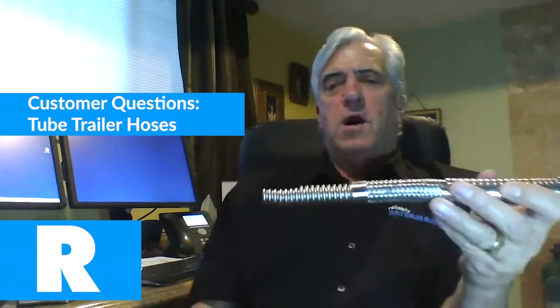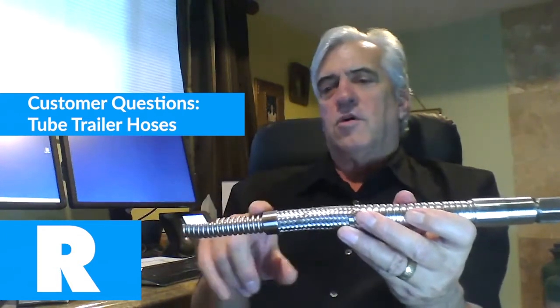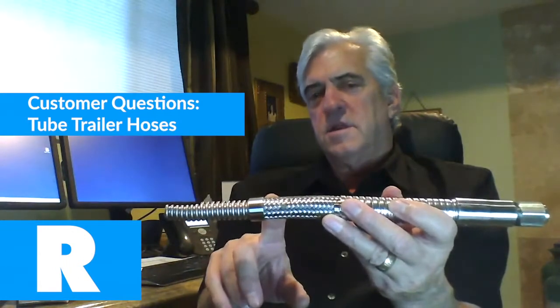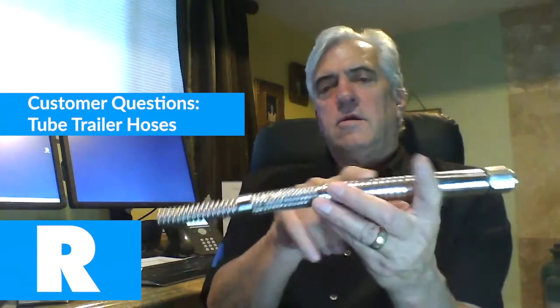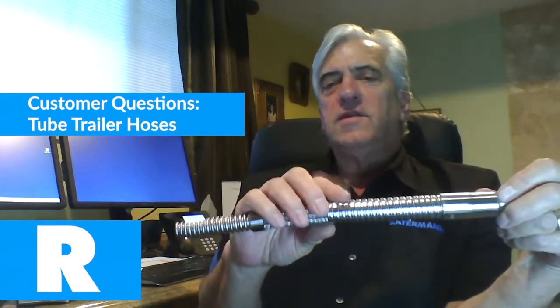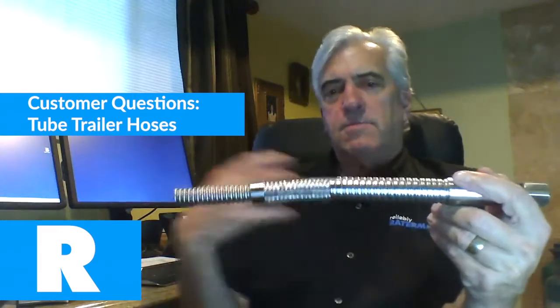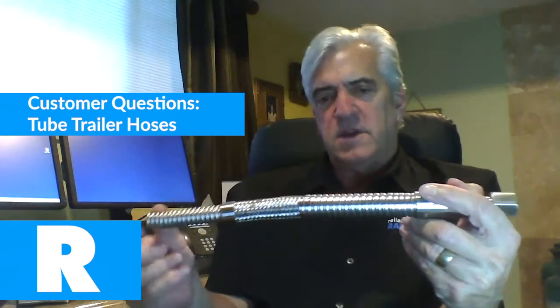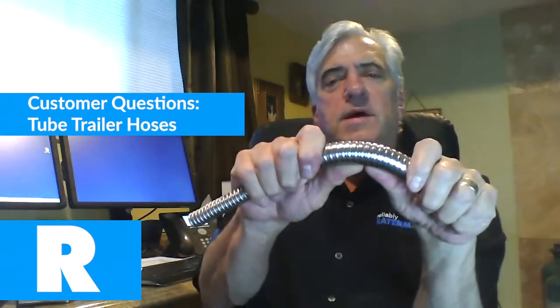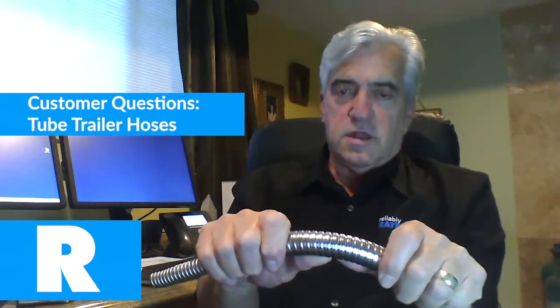So this is what the modern day flexible cryogenic hose looks like. You've got the corrugated inner core with layers of stainless steel braid, and right here is your armor casing. A lot of people ask, why do I need the armor casing? Well, not only does it keep your hose cleaner, keeps debris, dirt, and dust off of it, the biggest purpose of this is you cannot bend this beyond the hose's bend radius.